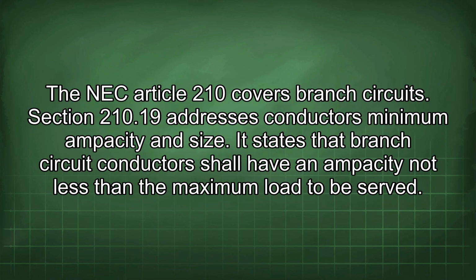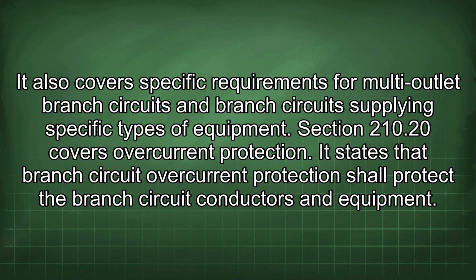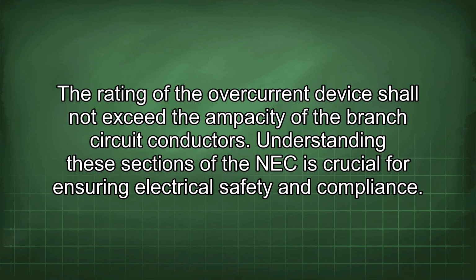The NEC Article 210 covers branch circuits. Section 210.19 addresses conductors' minimum ampacity and size. It states that branch circuit conductors shall have an ampacity not less than the maximum load to be served. It also covers specific requirements for multi-outlet branch circuits and branch circuits supplying specific types of equipment. Section 210.20 covers overcurrent protection. It states that branch circuit overcurrent protection shall protect the branch circuit conductors and equipment. The rating of the overcurrent device shall not exceed the ampacity of the branch circuit conductors. Understanding these sections of the NEC is crucial for ensuring electrical safety and compliance.